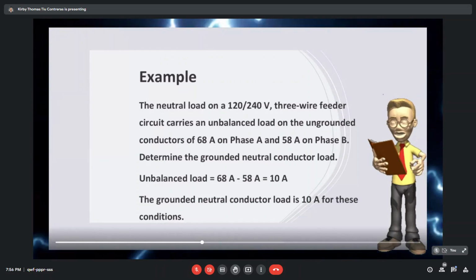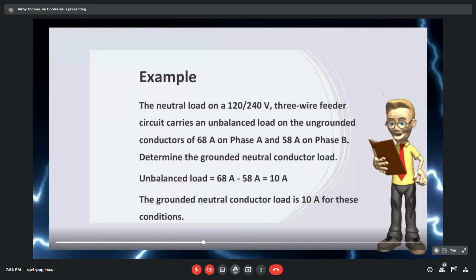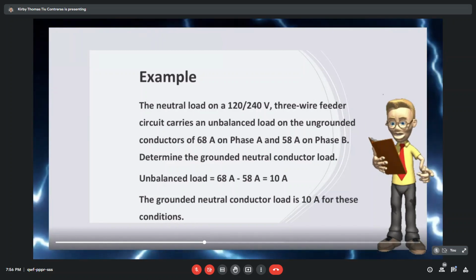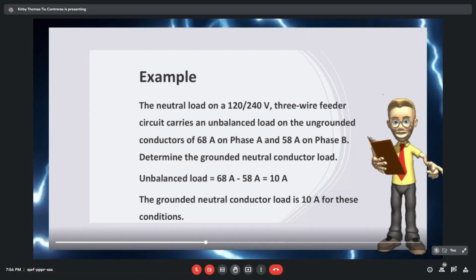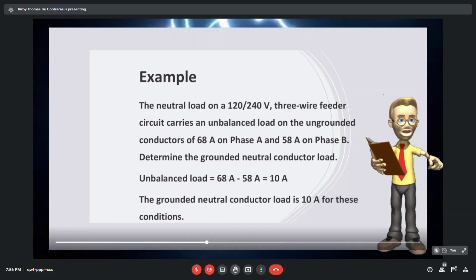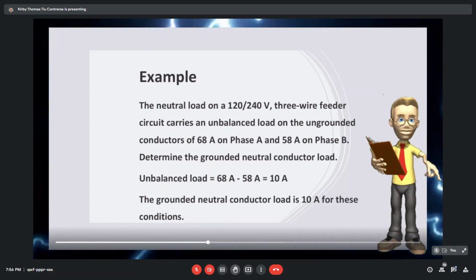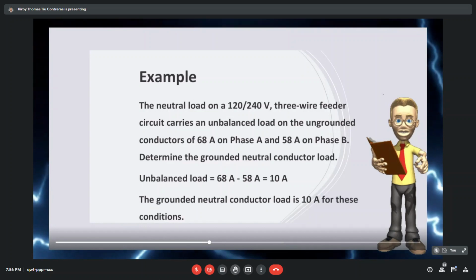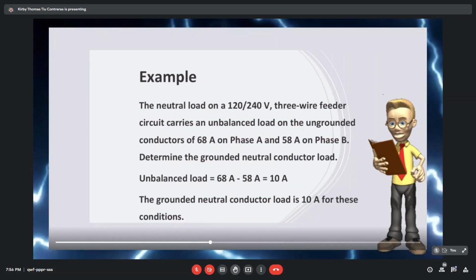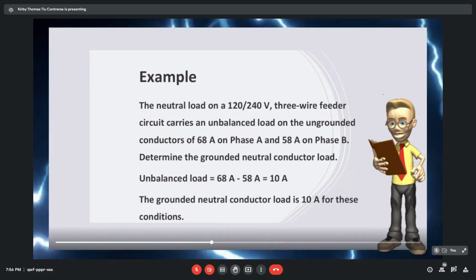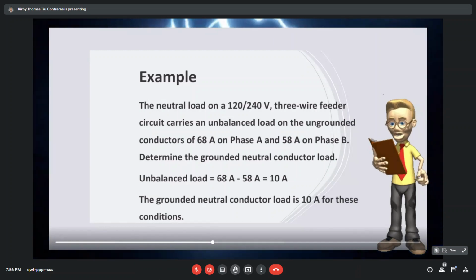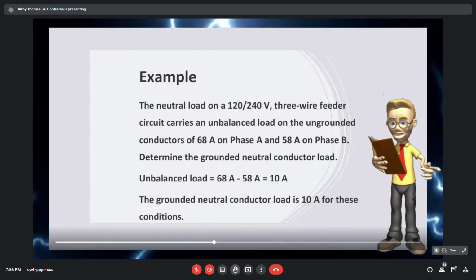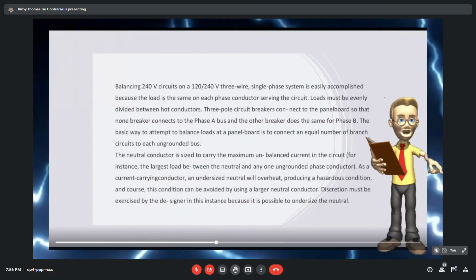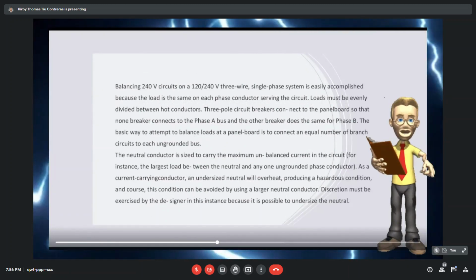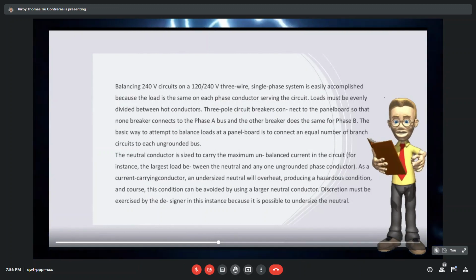Each of them is 120 volts to ground, and a neutral conductor is also present in 208 over 120 volts and 480 over 277 volts services, feeders, and circuits. Grounded and neutral conductors should always be insulated because they can carry current. They should be continuous because they provide a path to complete the circuit or circuits.